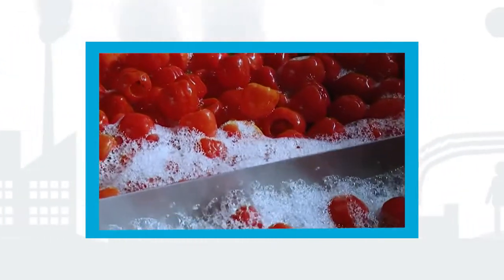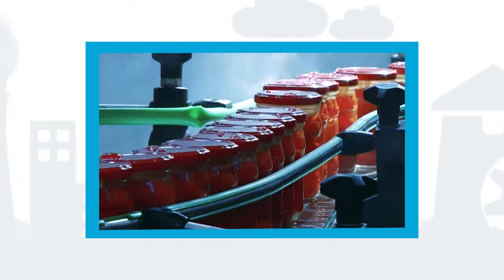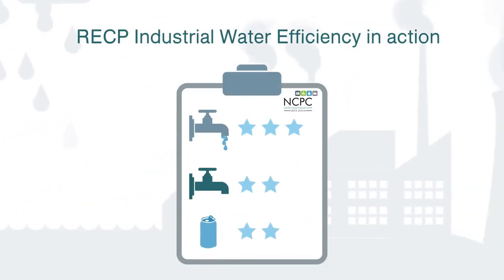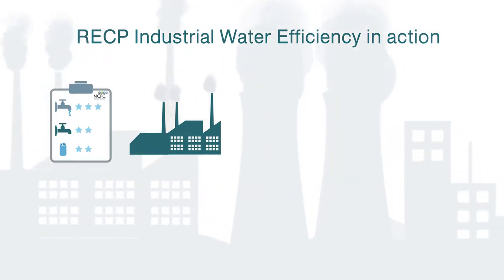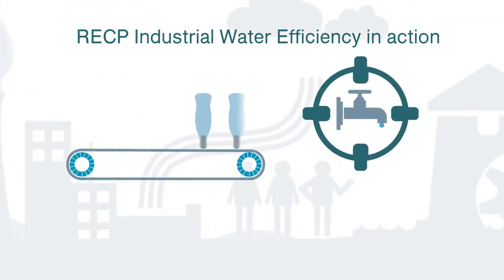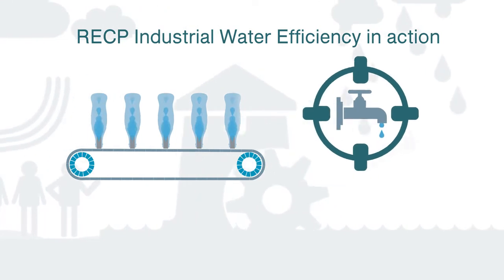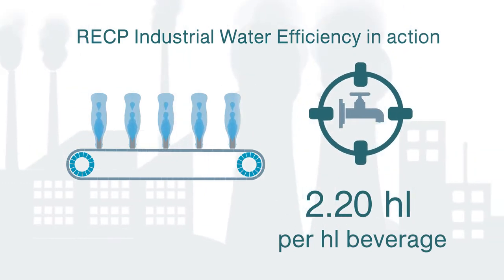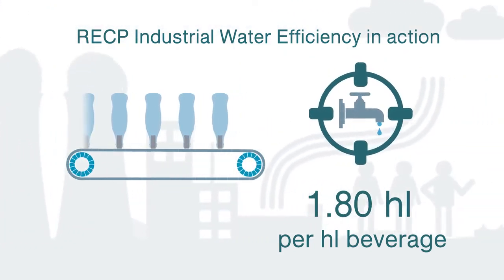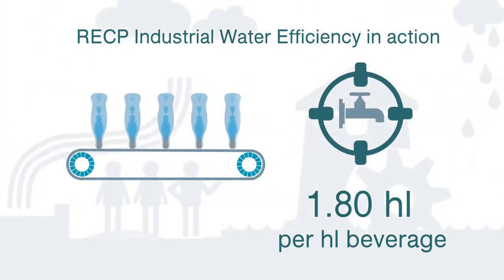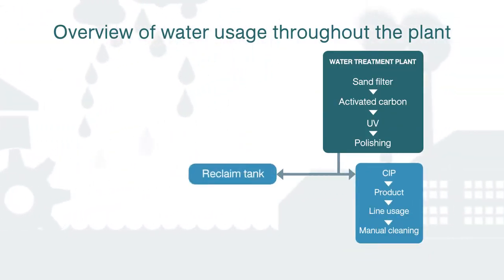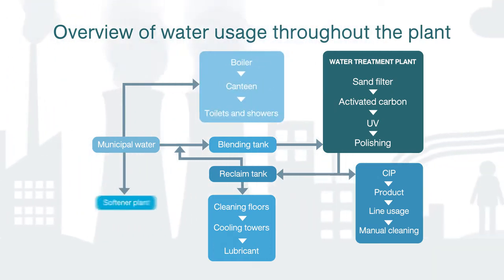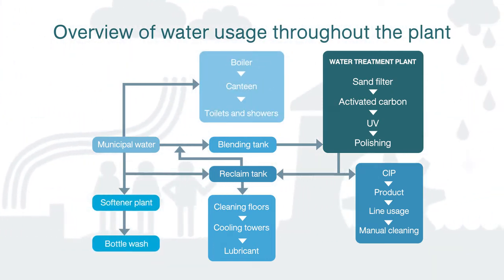Let's take a look at RECP Industrial Water Efficiency in action. The NCPCSA conducted an assessment at a proactive, high-profile international soft drinks group. The plant had tight targets for water use management and reduction, which included a self-imposed reduction target aimed at reducing specific water consumption from 2.2 down to 1.8 hectolitres of water per hectolitre of beverage produced. In the assessment process, a detailed site water balance provided an overview of where and how much water was being used in the process.